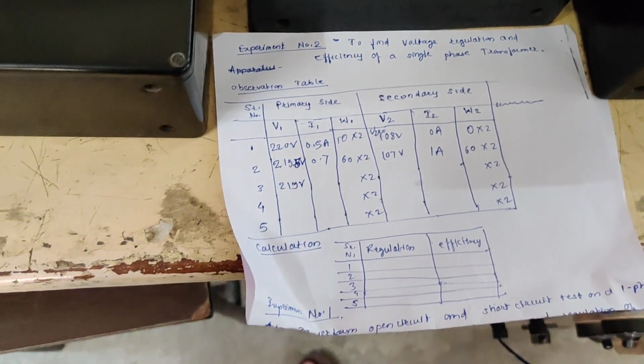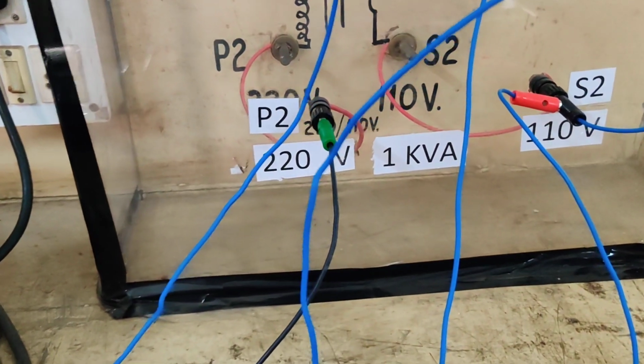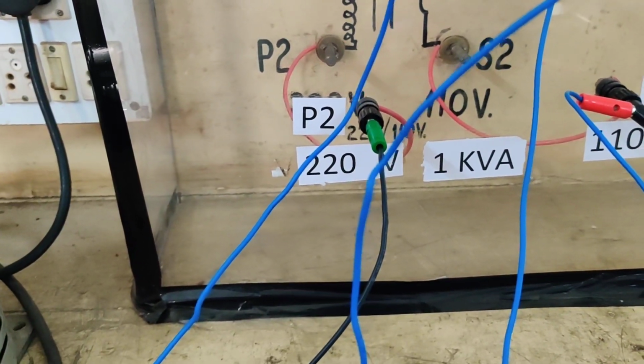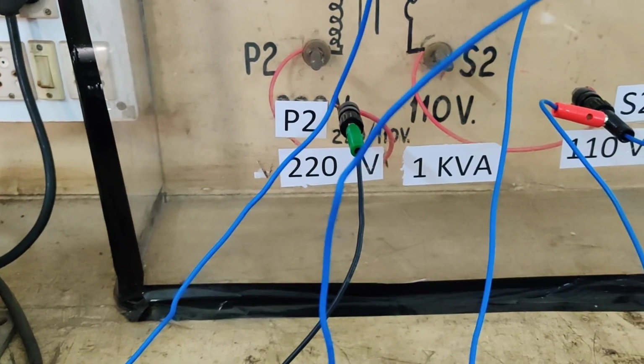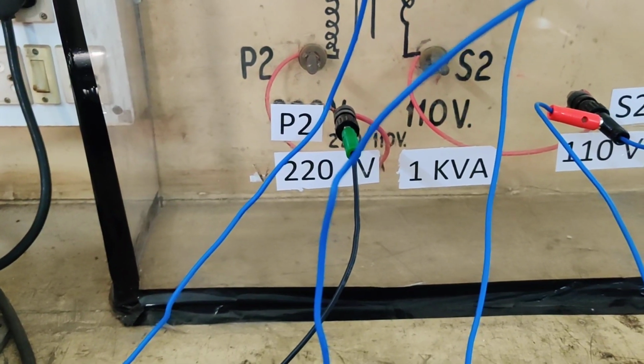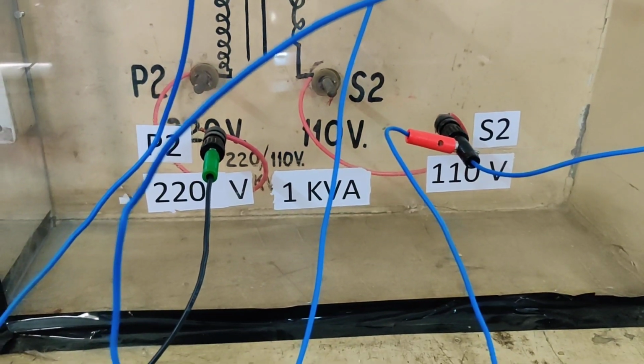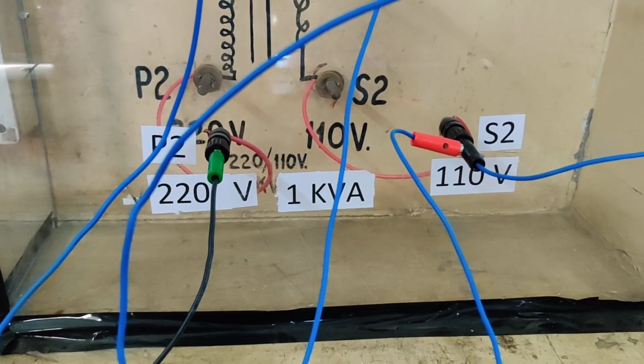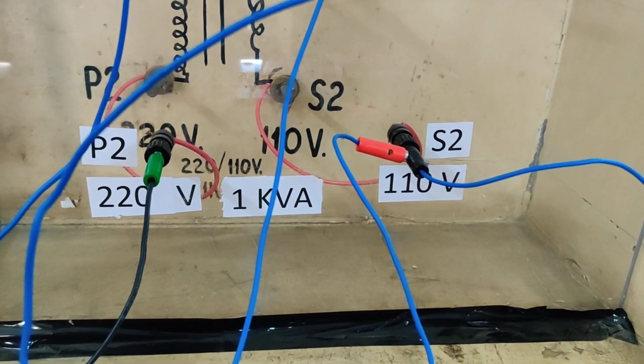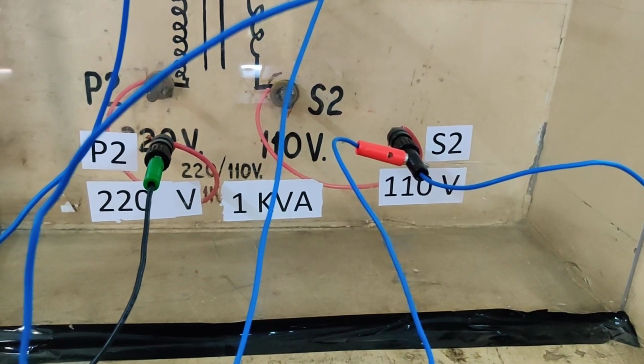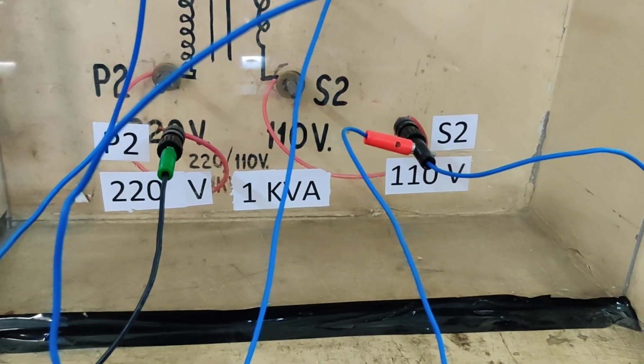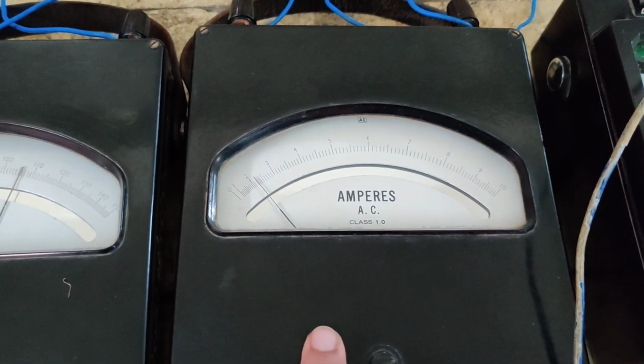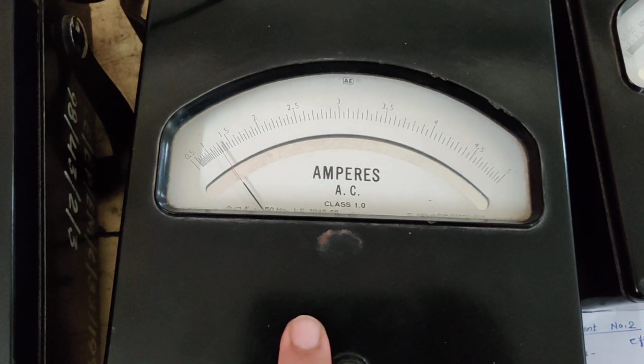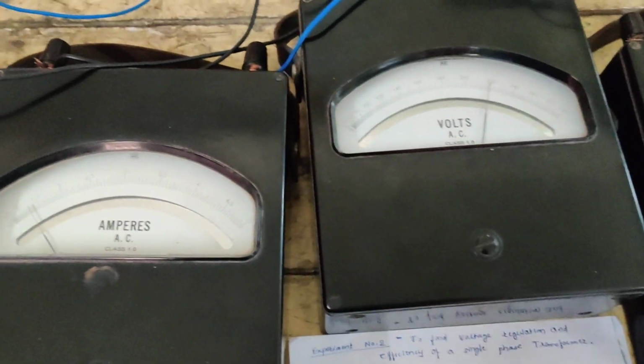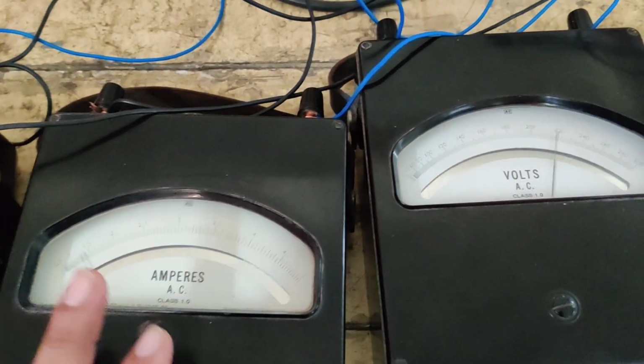How should we calculate the rated current? So rated current will be 1 kVA divided by 220 volts. So what will be the current? The primary current will be 4.5 ampere. Secondary side 1 kVA, that is 1000 volt ampere divided by 110 volts. So my ideal current will approximate 8.9 ampere. So either here on the secondary side 8.9 ampere will become, or here we can measure the 4.5 ampere. So either of the situation if we have, then we have to stop the reading.